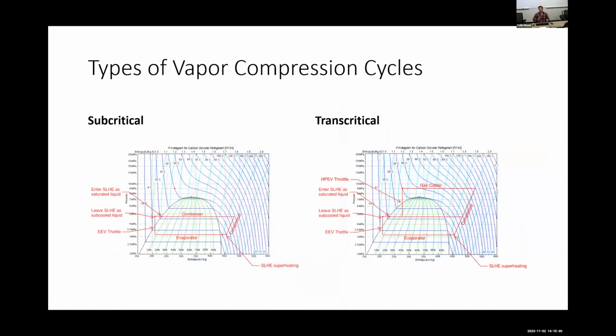All right, so there's two types of vapor compression cycles, or at least I'm comparing two that I'm familiar with here: subcritical versus transcritical. So really the only refrigerant that I've seen used in a transcritical cycle is CO2. It has a very low critical point. It goes transcritical in a regular chiller, depending on what type of condenser you would have. It's like 70 to 80 degrees outside, it's going to switch to transcritical.